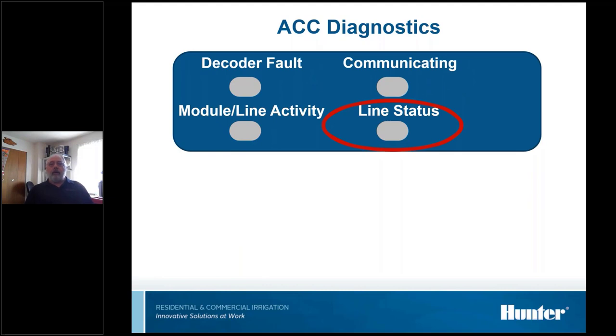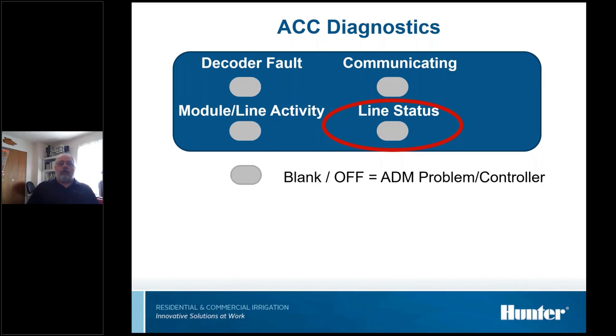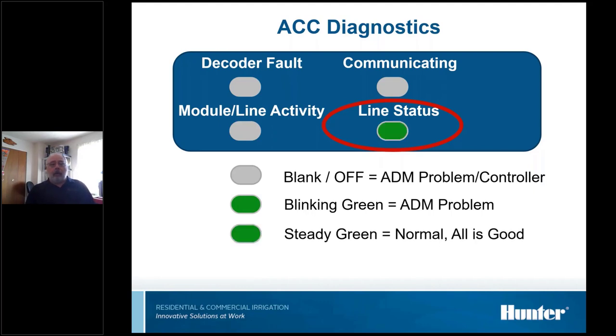The one thing I tell everybody, just remember, green is good. So if this light is blank when you open up the controller, that module is probably shot. It could be the other module in the controller that we call the master module, but usually if that light is out, the ADM99 module is bad. And if it's blinking green, and it seldom is, but when it's blinking green, that module is definitely bad. Replace it. And then green is good. Steady green is what we want to see. I say if all you remember is green is good, then you're getting something out of this.